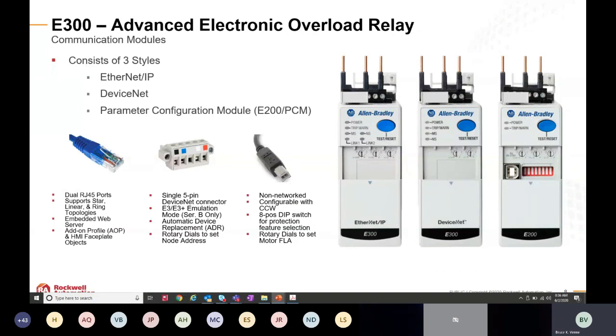And then as I mentioned, that third module is the communication module that sits on the top of the E300 stack, the three different flavors there: Ethernet IP, DeviceNet, and then the E200. I won't go into too much detail on these because we've already talked about this at great length. One thing to note, though, is that the E300, to use it in its full form, does require at least one of every module. So you need at least one sensing module, at least one control module, and at least one communication module.